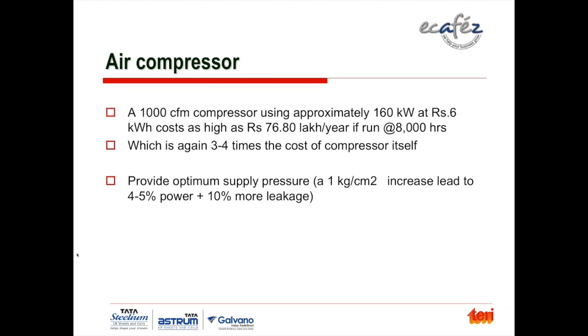A 1,000 CFM air compressor running for 8,000 hours in a year could lead to an electricity bill of 76 lakhs. So the running cost of the air compressor is almost 3 to 4 times the cost of the compressor equipment itself. And here there are many tips for saving energy.